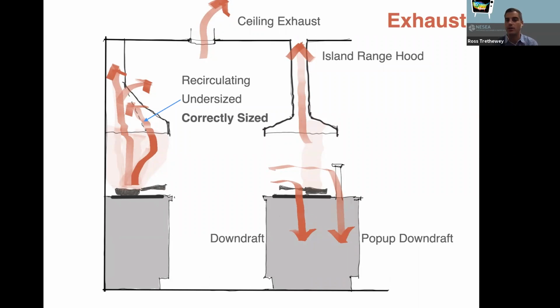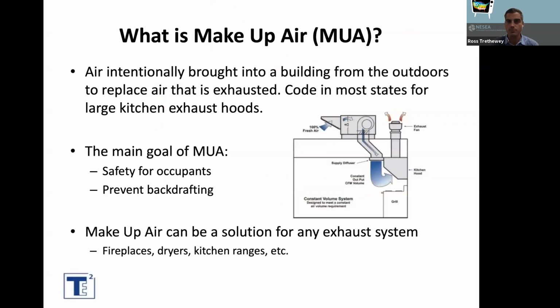You need that kitchen hood to be correctly sized. The rule of thumb is that it should be at least the square footage coverage rate of the cooking surface, and the deeper, the better. The deeper the volume of the hood, the better capture efficiency it's going to have. So we can keep going.